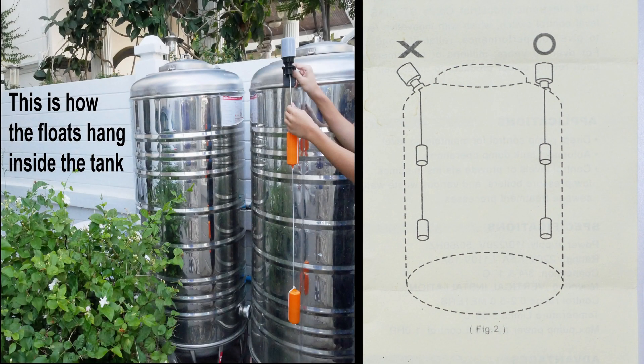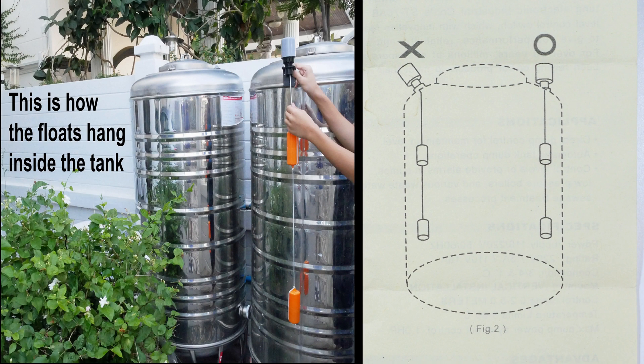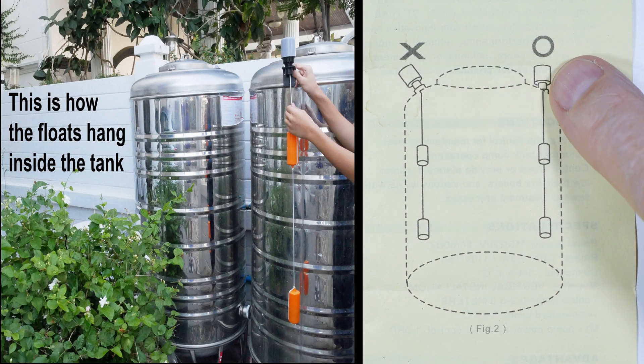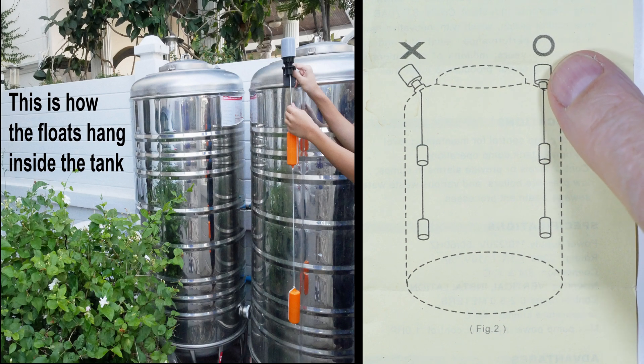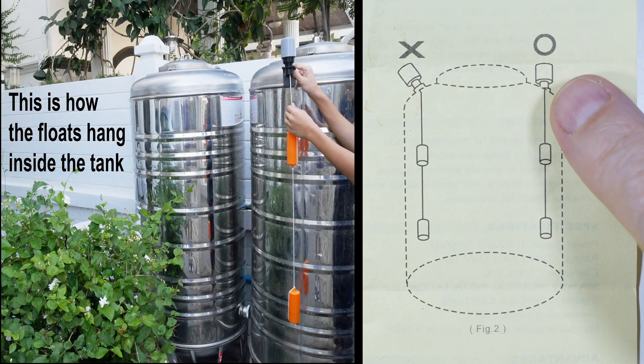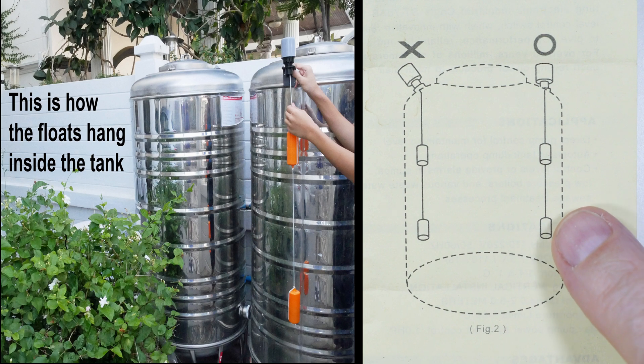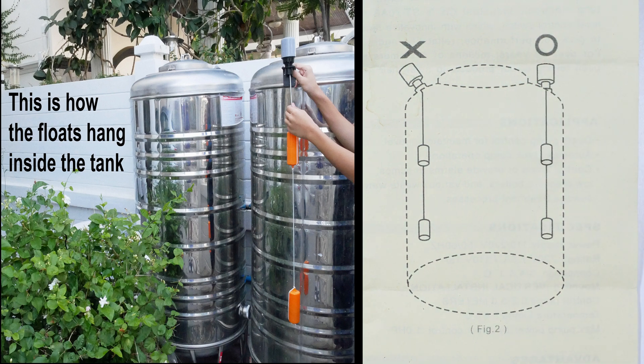In my solar applications where I've used this in water tanks to fill water tanks, one problem I've found is that the switch is mounted on top of the water tank and it passes into the tank. We'll do a close-up here in a second. The air above the water is saturated with moisture, and as soon as the temperature goes down, I've had serious issues with condensation inside the switch, really shortening the life of the switch.